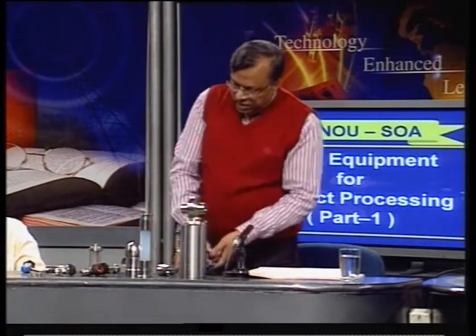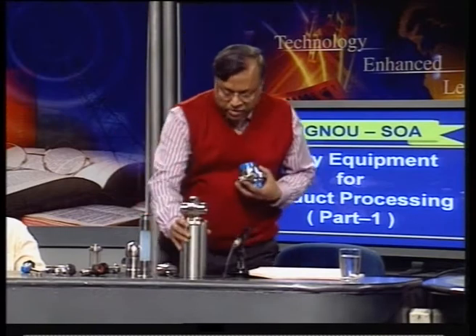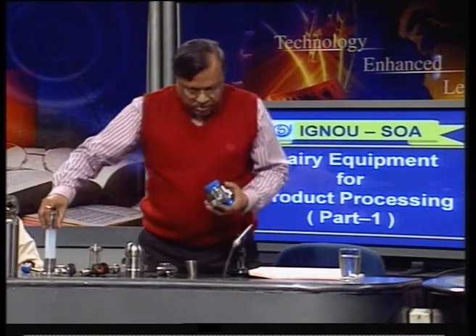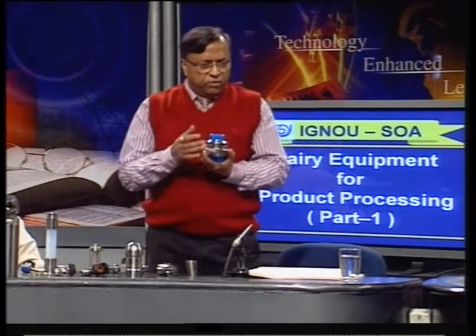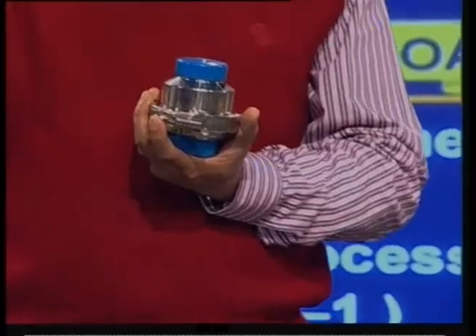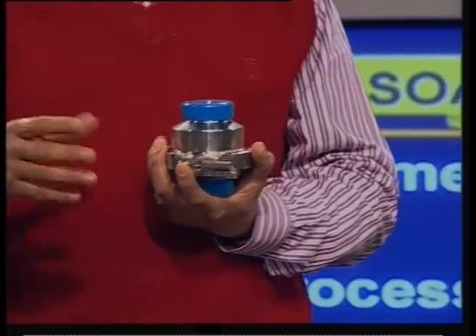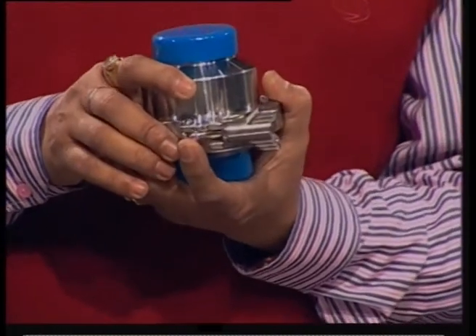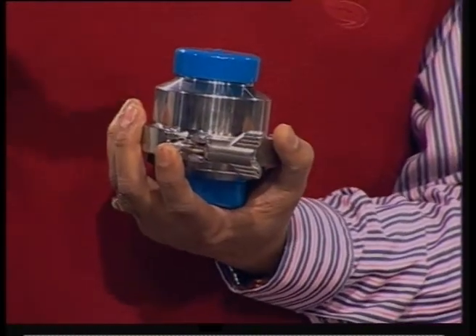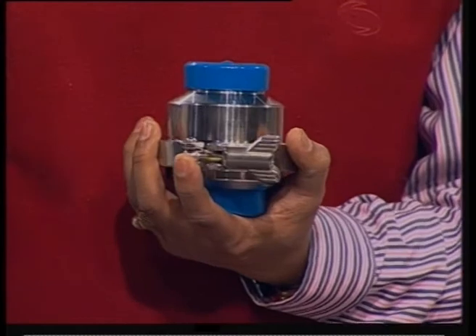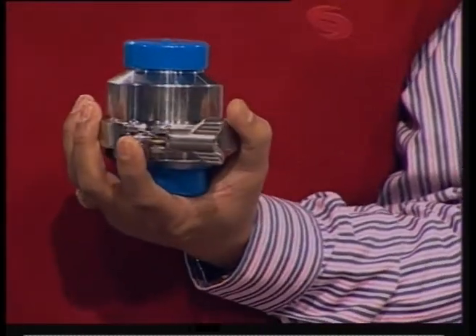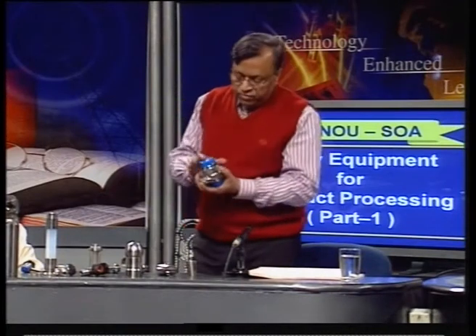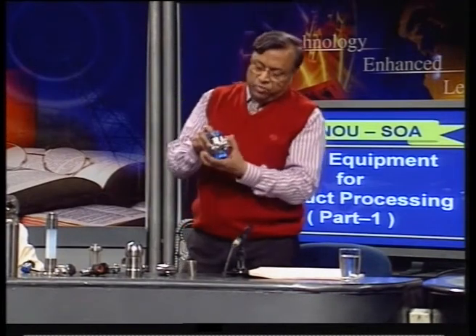Next we have a check valve. The check valve is used in lines where we do not want the product to come back into the system. For example, at the discharge of a milk pump — if you put a check valve, the product going up to the silo will not drain back through the pump to the drain. So we put the check valve to save that product.